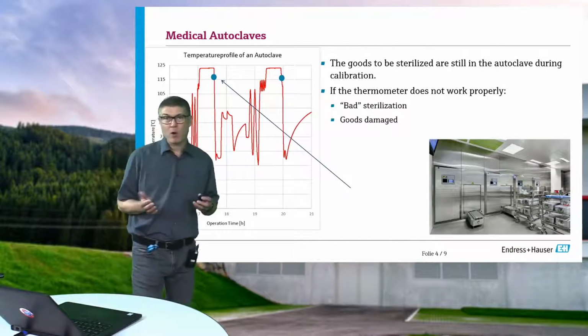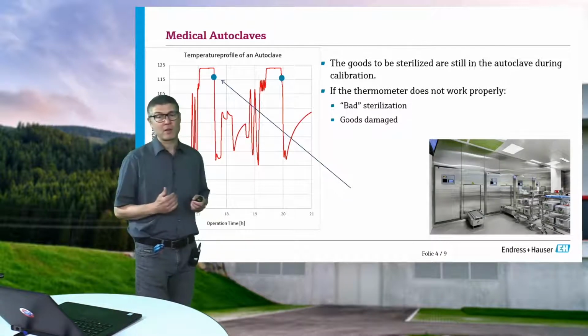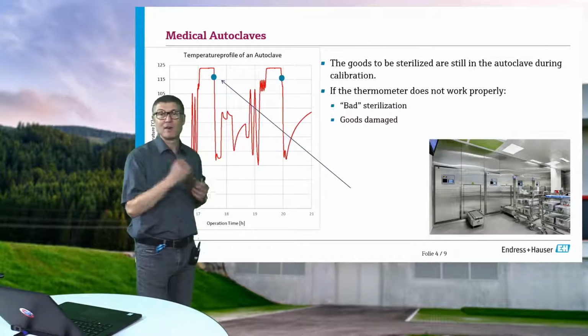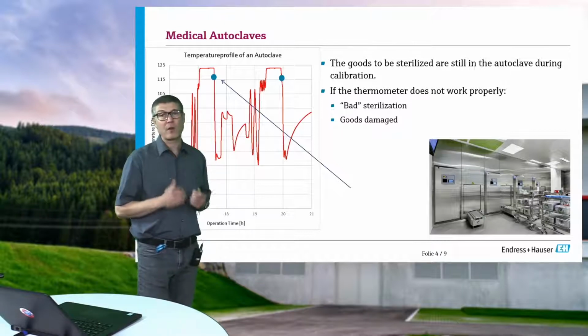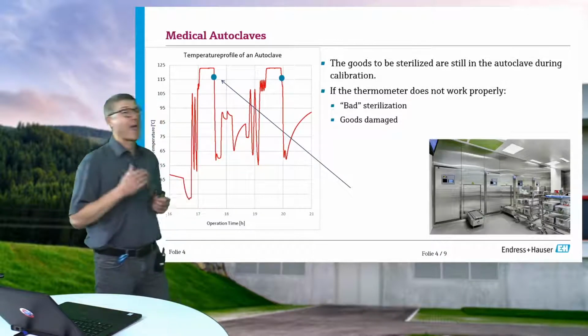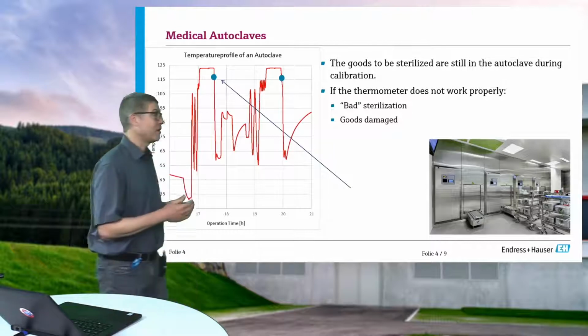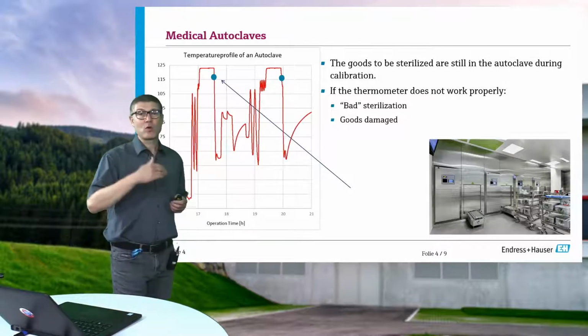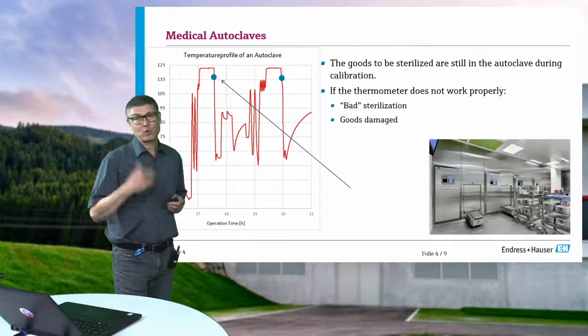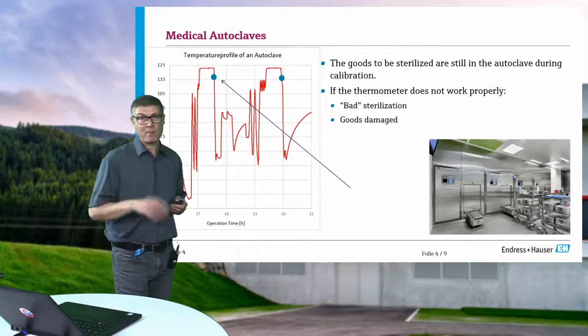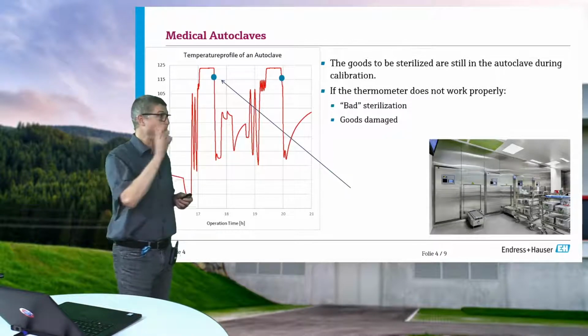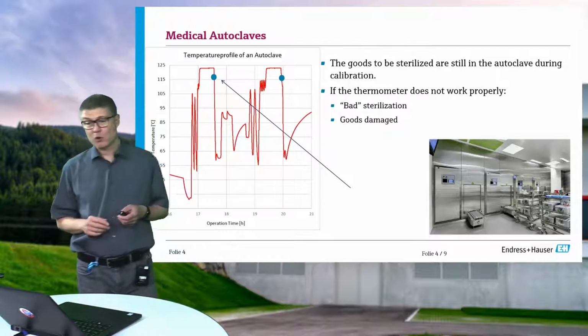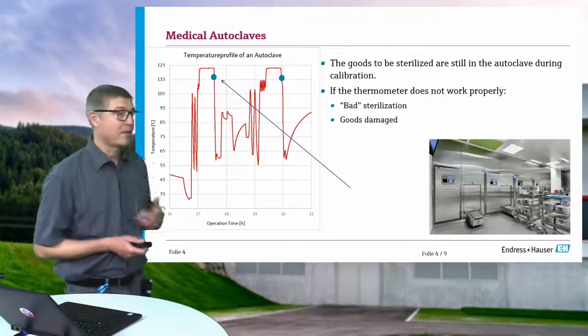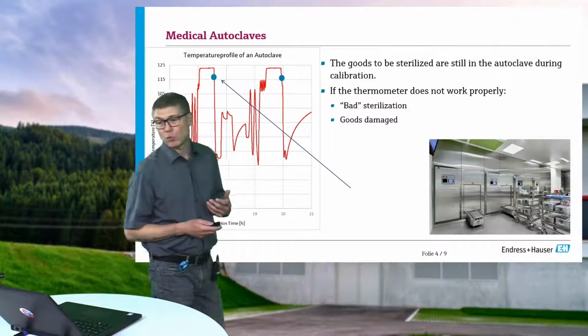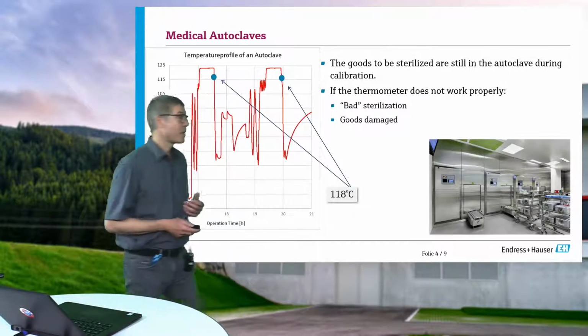It's the same story, more or less. You need to reach a certain temperature, really here to kill all germs, to kill all bacteria and viruses. And again, it's necessary not to go too high because maybe you damage your product if you have some medicine in it or whatever. Again, you need an accurate temperature measurement, and the only way to save this for the future is to do a calibration.